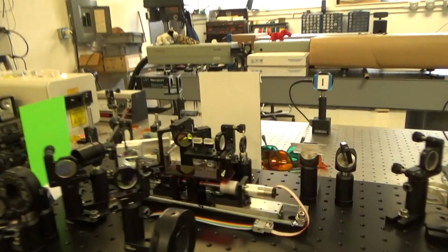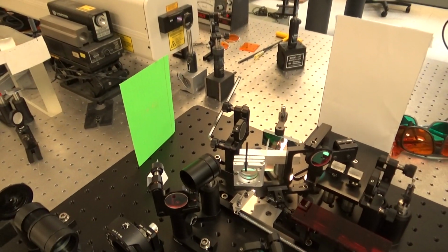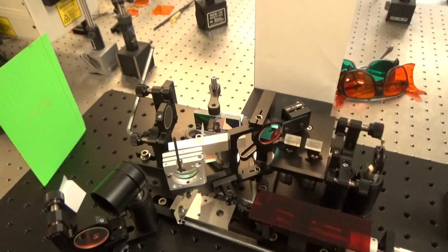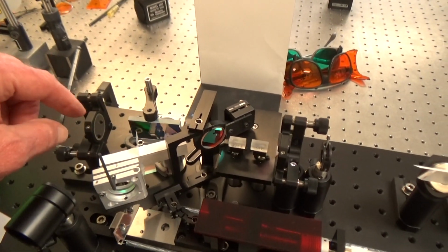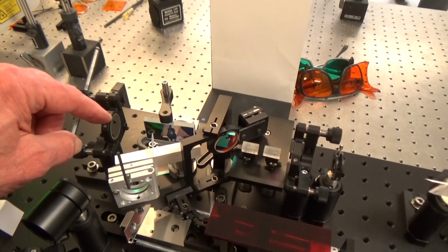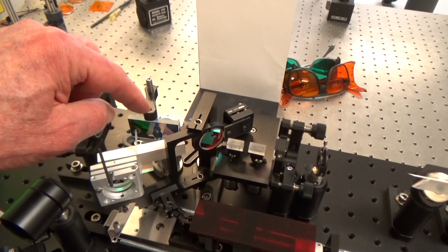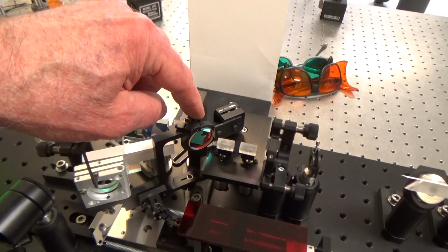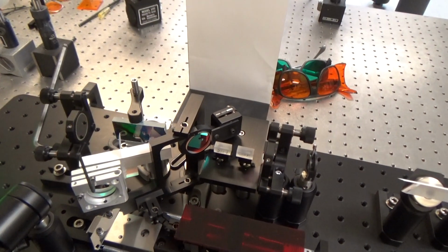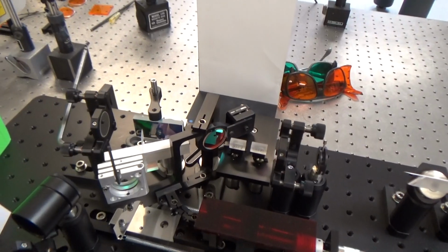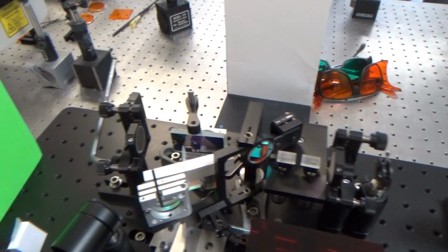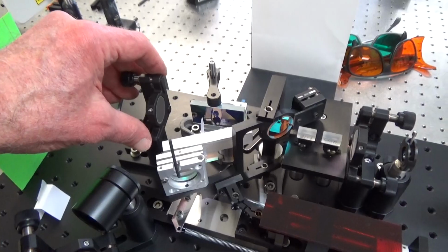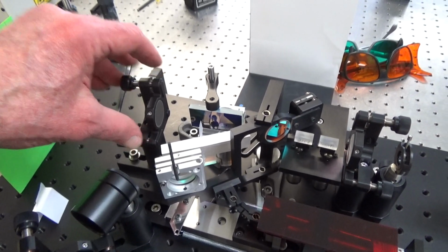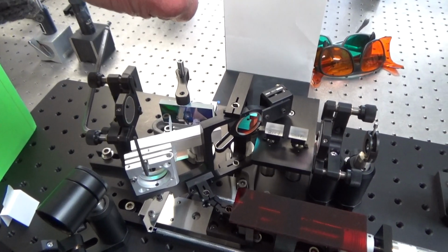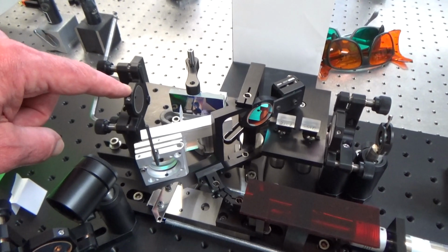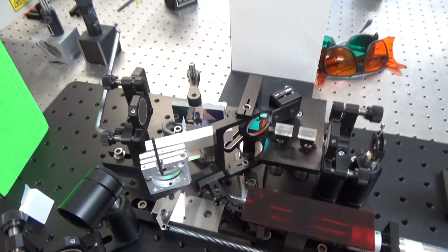Okay, now for putting the rear mirror back in again, you want to put it in place so that it is reflecting the green light back off the grating again. That will all be reflected by HR3, and you'll see a second spot on the rear wall. There is another configuration for the rear mirror: if it's a little more clockwise rotated, you can miss the grating and also see another spot. So just make sure that the spot you're seeing is the one that's reflecting off the grating.